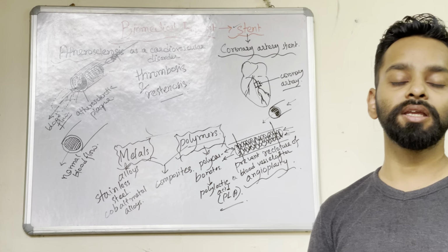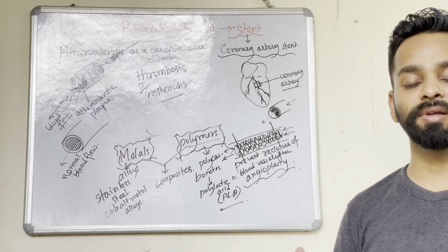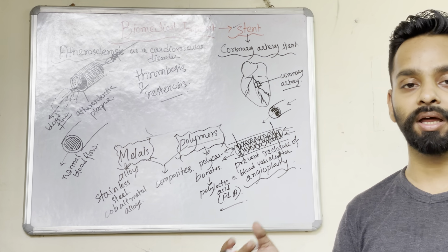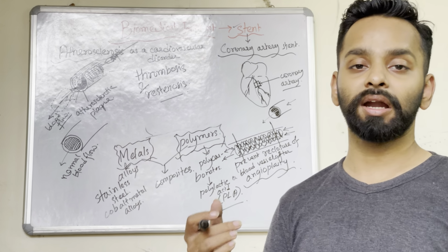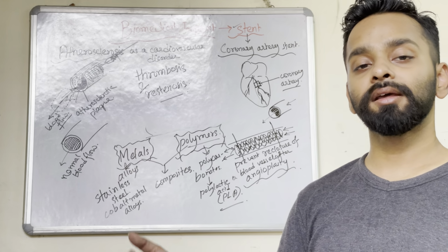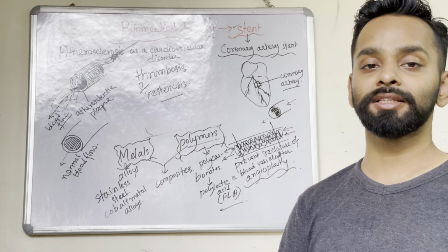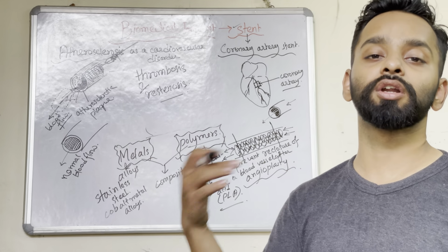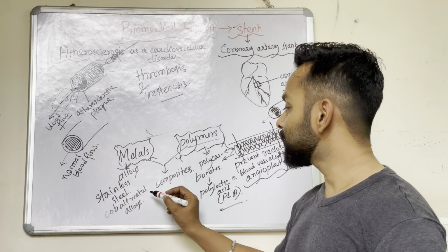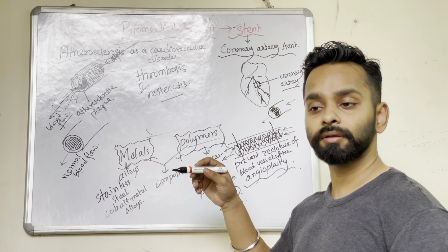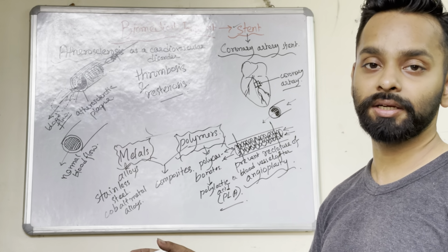These terms essentially mean clot formation and narrowing of the artery in which the stent is placed, because the stent will interact with the blood, and therefore the clotting cascade, the pathway which is responsible for blood clotting, will be activated, and the clot will again form on the surface or on the periphery of the section where the stent is placed, and that will again lead to closure of the artery and reduced flow of blood through that section. So it is not desirable that these stents be kept in a cross section of an artery for a very long time.